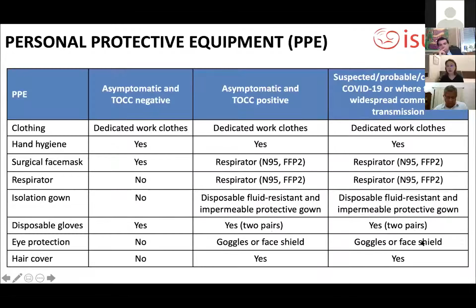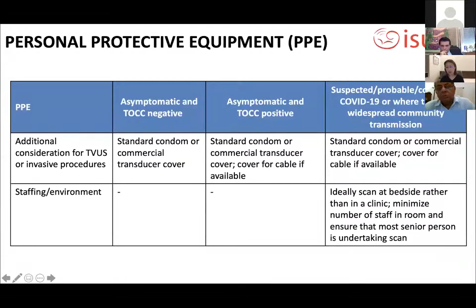And in relation to the use of transvaginal ultrasound as well as invasive procedures, you need to make sure you cover the transducer by using either the standard condom or a commercially available transducer cover. And in those with suspected, probable, confirmed COVID-19 infection, or where there's widespread community transmission, you should also consider covering the cable. In relation to staff environment, we believe the last group should have a bedside scan rather than in a clinic. You need to minimize the number of staff in the room, and you should ensure that the most appropriate person undertakes the scan in the shortest period of time.